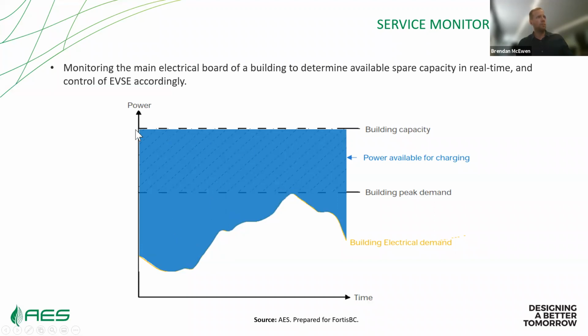Typically, buildings almost never use their full capacity. The electrical code is inherently conservative, so there's tons of remaining capacity. Without these systems, according to the electrical code, you'd only have the capacity between the building's peak and the transformer capacity. But with service monitoring and energy management systems, you can use all that remaining capacity below the peak line.